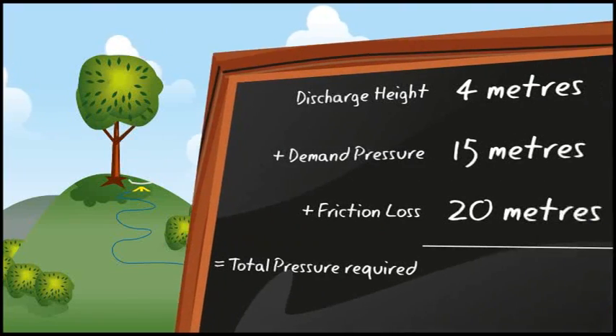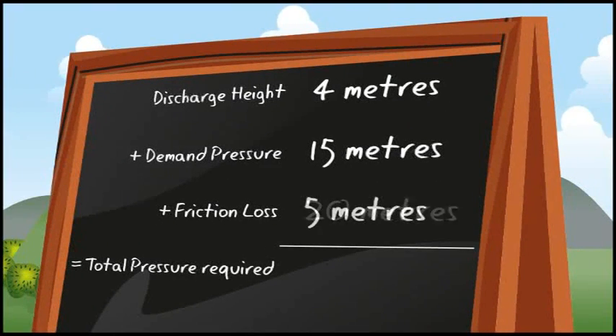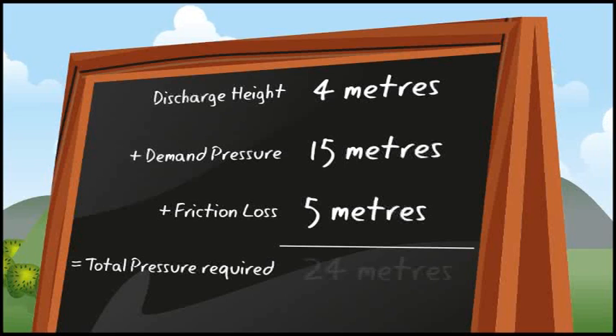On our calculations, we change our friction loss from 20 metres to 5 metres. Add these three amounts together and we have the new total amount of head or pressure required. In this case, 24 metres.